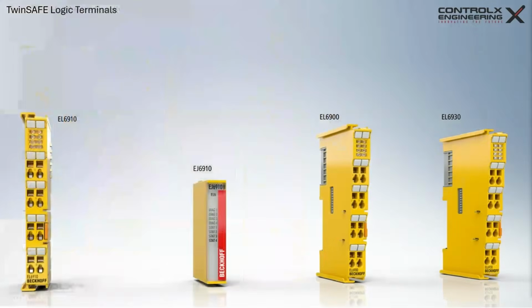Let's start with the TwinSAFE logic terminals. What is a logic terminal? In simple terms, it's a safety controller, which means it is a dedicated device that executes safety logic independently of your main PLC, and is the link unit between the TwinSAFE inputs and outputs. Instead of relying on the standard control task, all safety-related decisions, things like emergency stops, guard door monitoring, muting, or safe motion conditions, are handled inside the logic terminal based on the logic programmed by you.